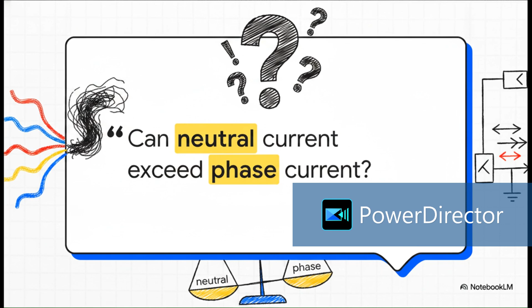Or does it? Section 1, the plot twist: enter nonlinear loads. Throw standard logic out the window, because in a real industrial environment the rules completely change. We're talking about nonlinear loads, specific pieces of technical equipment, the industrial suspects: uninterruptible power supplies, switch mode power supplies, and variable frequency drives. I guarantee if you walk into any modern industrial workplace today, you'll find these machines connected to the system 100% of the time.